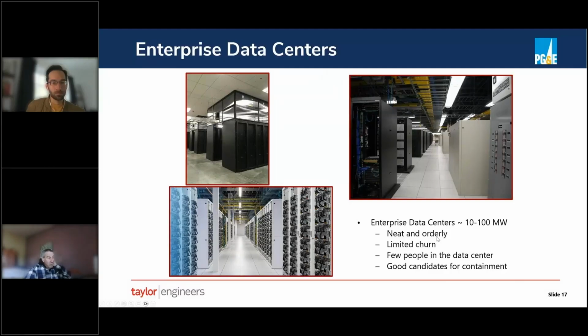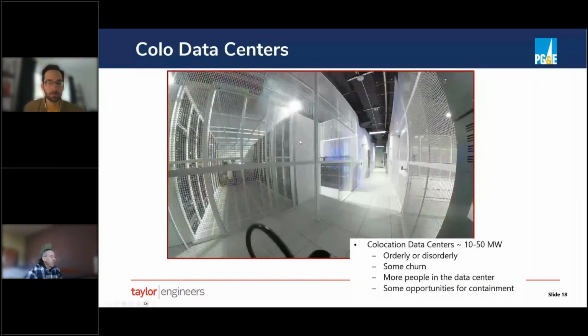So one of the main characteristics of an enterprise data center is that it's fairly neat and orderly. You can see it's repetitious. Everything is clean. There's not a lot of people. Containment is definitely the standard of care for all data centers. It's required in California of this type. Here's a photo from one of the colos that we've worked in. They're often separated into cages for security and privacy reasons, not necessarily as well laid out and as orderly as the enterprise. Tenants are moving in and out. Containment is harder to control. You can see there's a person over here. Often tenants need to be in their spaces, so it's a little harder.